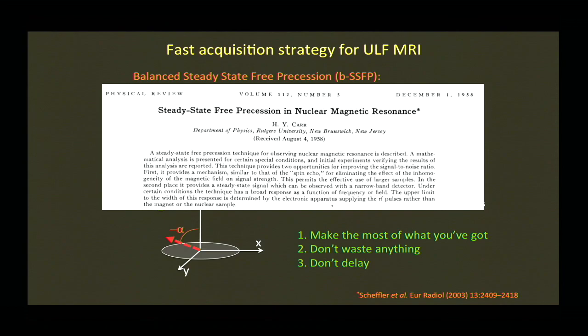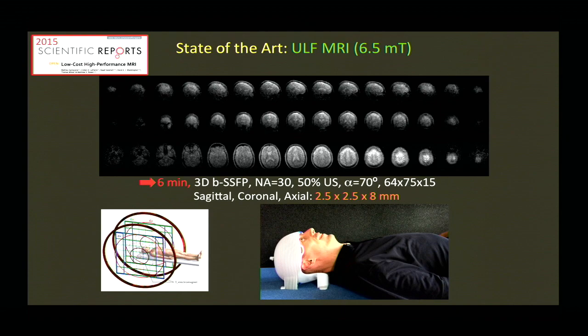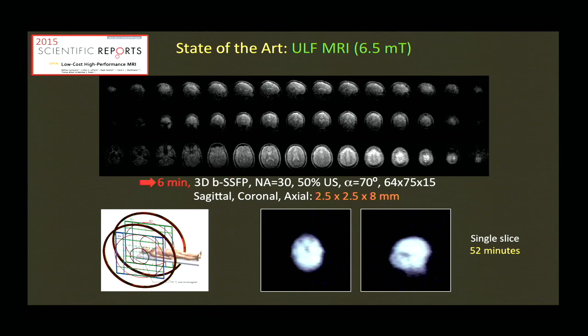Herman Carr in 1958 knew this — he wasn't doing MRI but was doing NMR at low field with long T1 samples. There is nothing new under the sun. In our scanner with SSFP, in six minutes we can do the same matrix size as before — roughly 2.5 millimeter in-plane brain imaging at 50% undersampling. Compare this to what I showed at the beginning: same scanner, different sequence. That gives you a sense that software is really valuable.